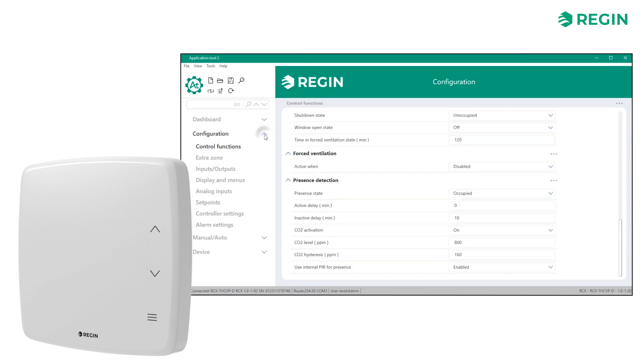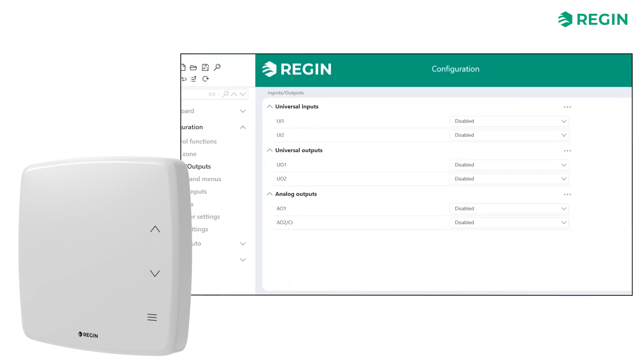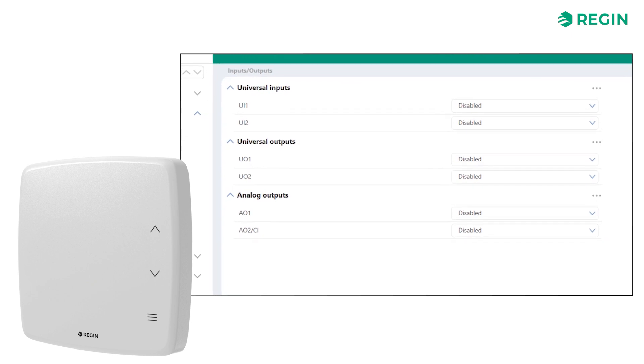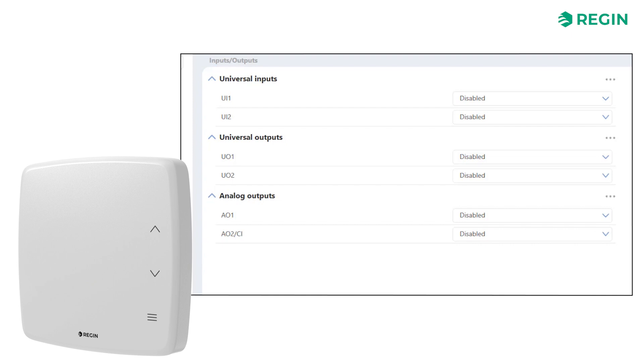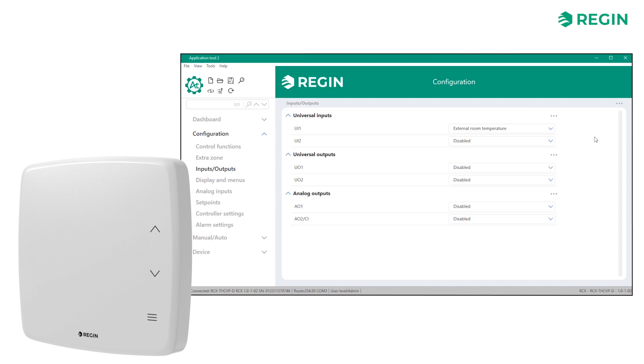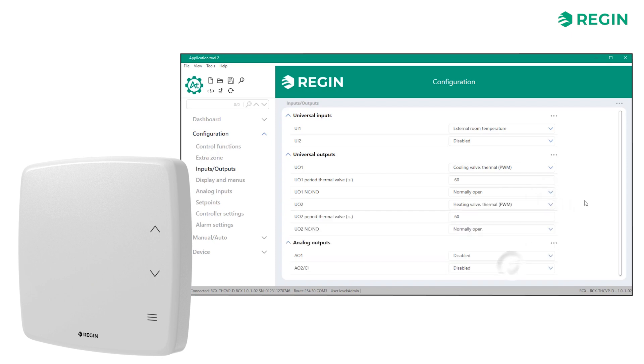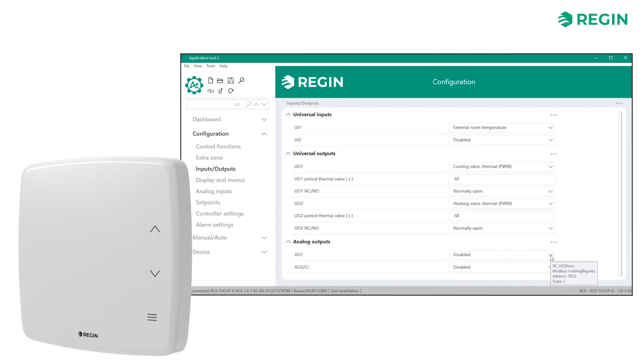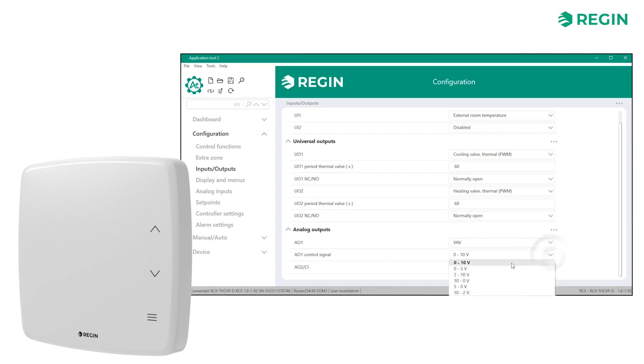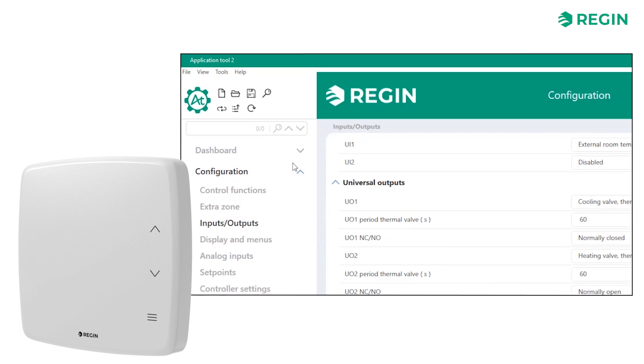If necessary, we can enable an extra zone to control heating or cooling. The next step of the configuration process is the Inputs and Outputs page. This is where we configure any additional inputs, other than the onboard sensors, and connections related to the sequences configured earlier. In this example, we will add an external temperature sensor to Universal Input 1. As for the outputs, we will add a thermal cooling valve to Universal Output 1 set to Normally Open, a thermal heating valve to Universal Output 2 set to Normally Open, and VAV to Analog Output 1 with a 0–10 volt control signal. Analog Output 2 can also be used as a condensation input, intended for Regin's condensation detector KG-A-1. When finished, let's load the new settings to the controller.